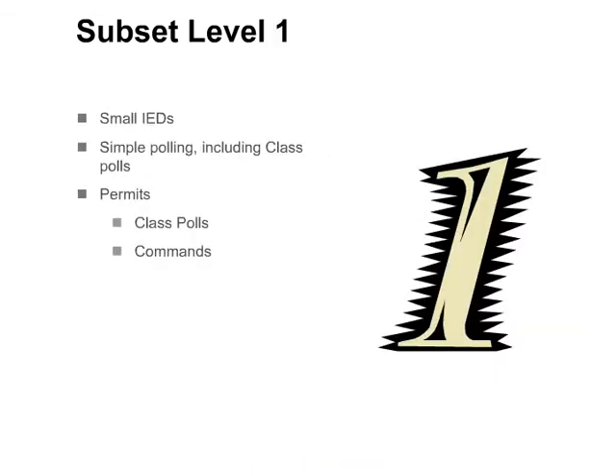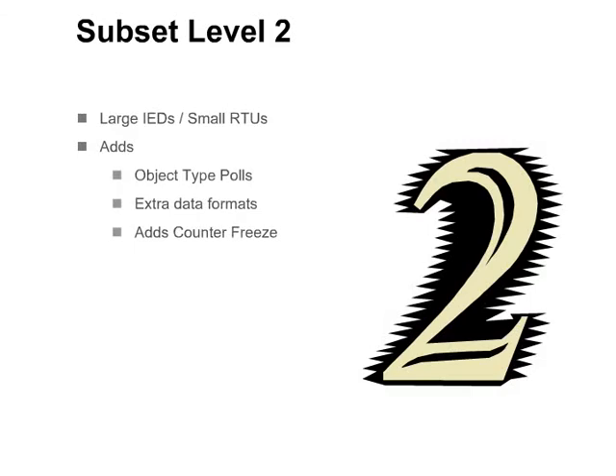Subset level 1 is designed for small IEDs. It uses simple polling, including class polls, which will be described later. Subset level 2 was designed for large IEDs or small RTUs. It adds object-type polls, extra data formats, and other useful features such as counter-freeze operations.